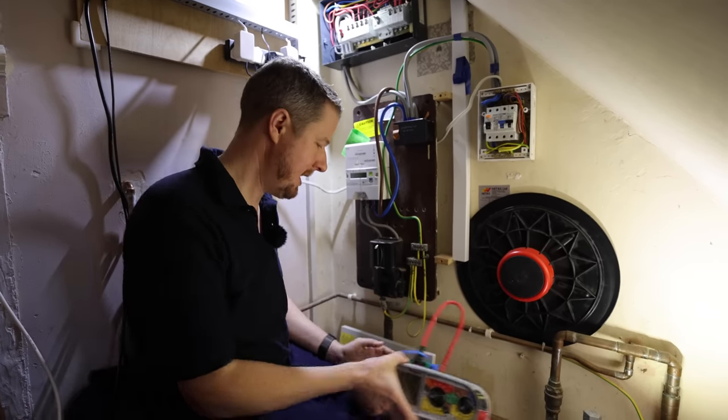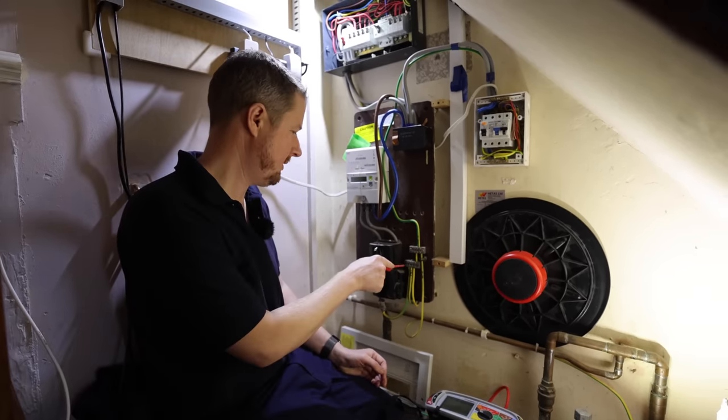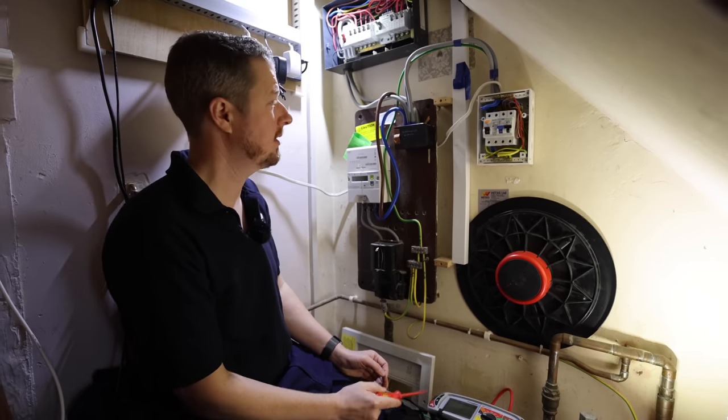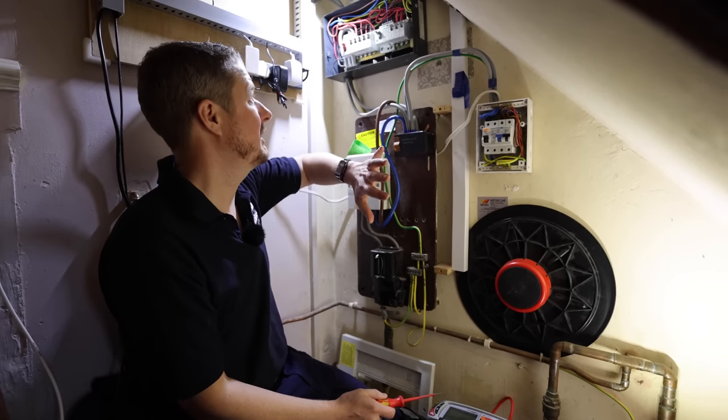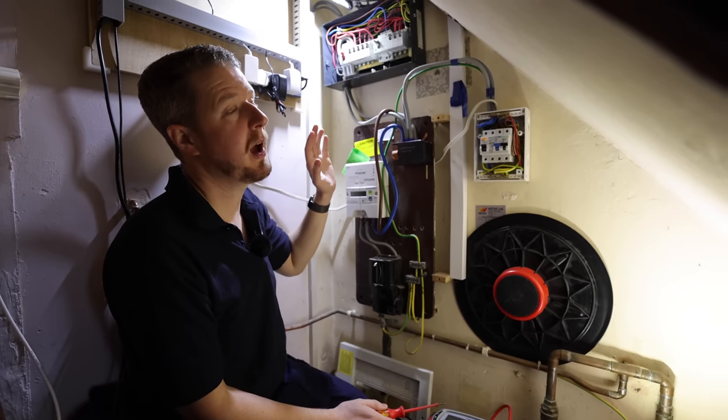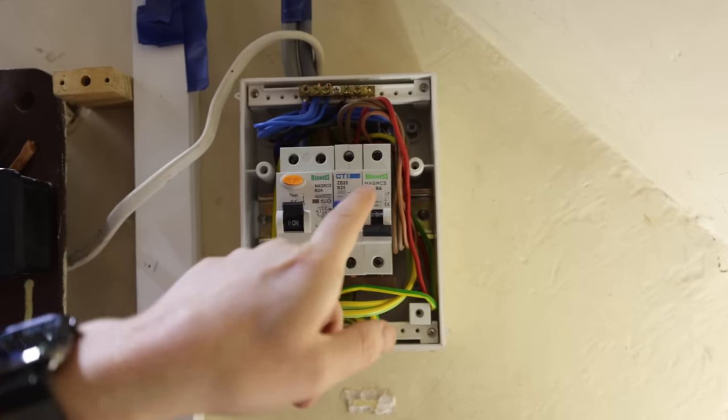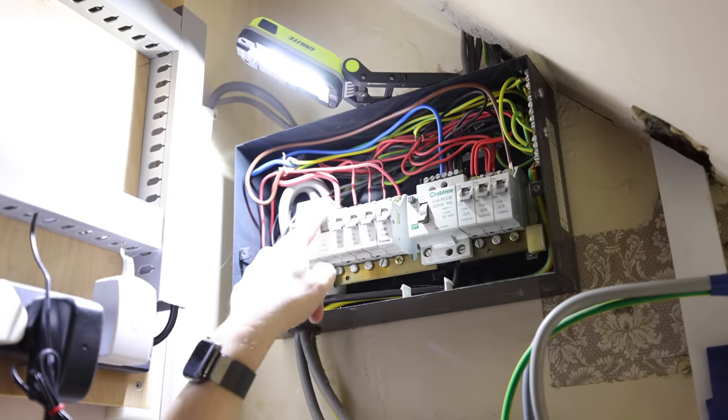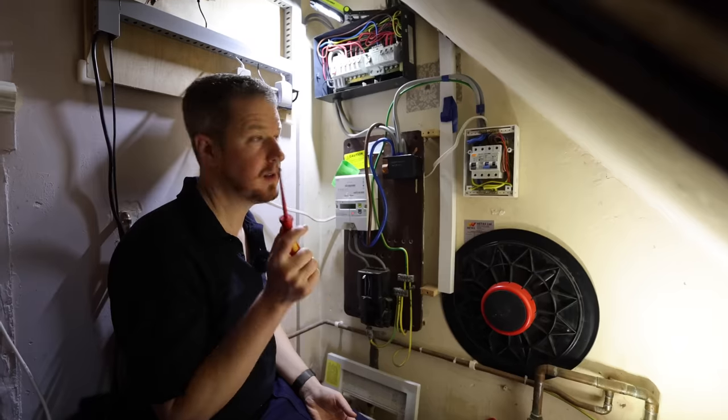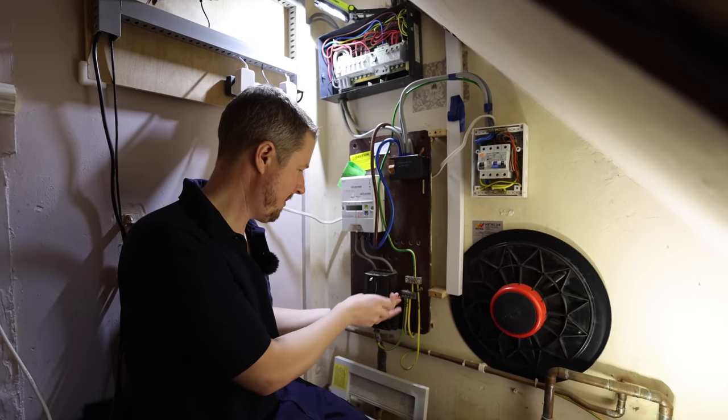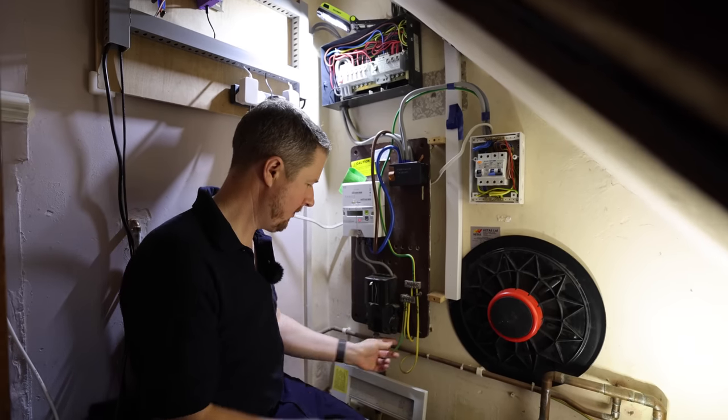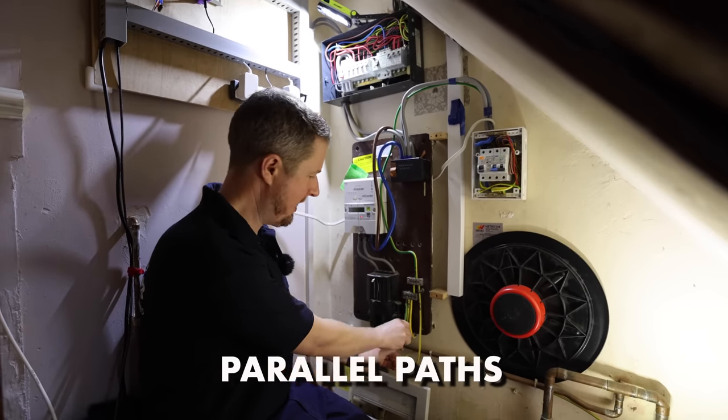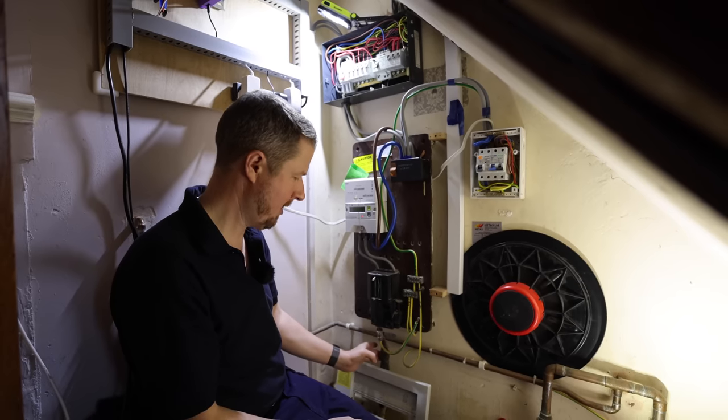Here we've got our first test reading to input, which is our external fault loop impedance, so we'll do that now. So first test we're going to do is our Ze, and to do that what we've got to do is disconnect our main earthing conductor and we've got to basically turn all the power off first. So power's going off, Lee, okay? So now our power's turned off, we're going to disconnect our main earthing conductor from here.